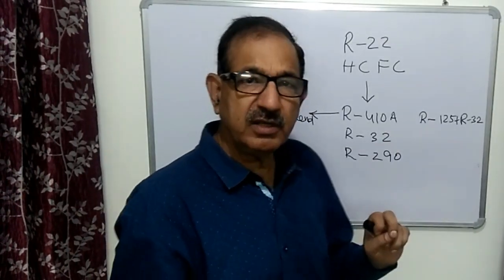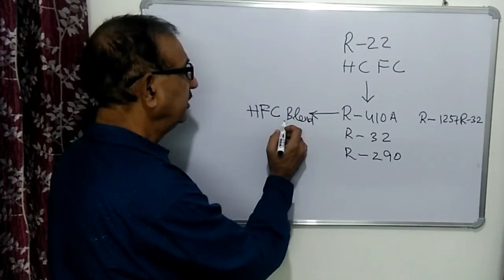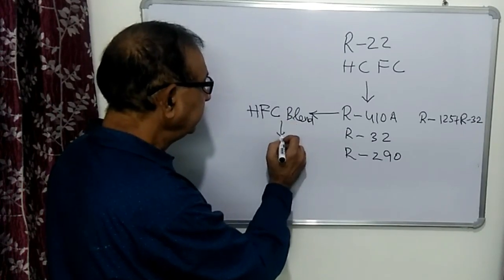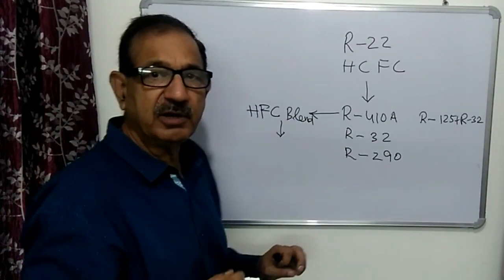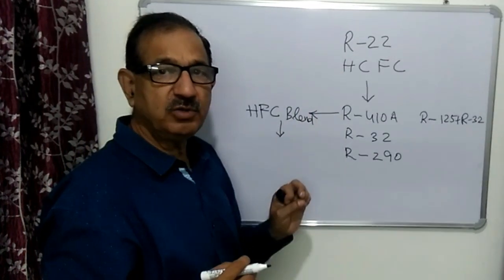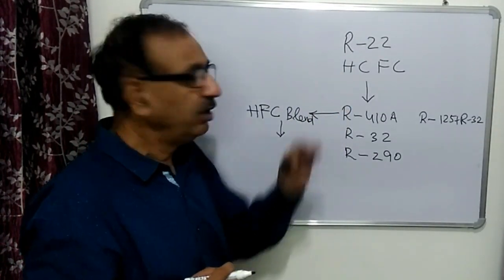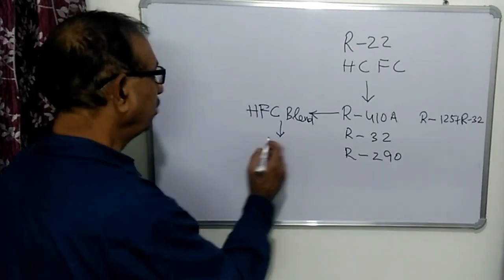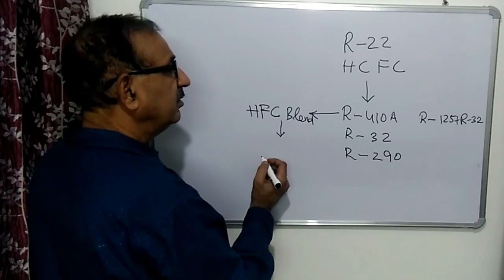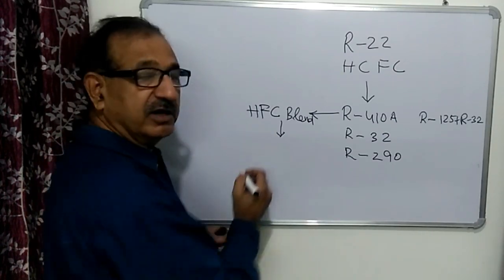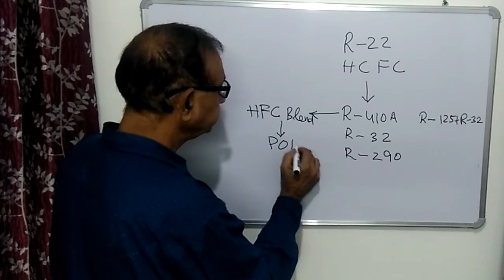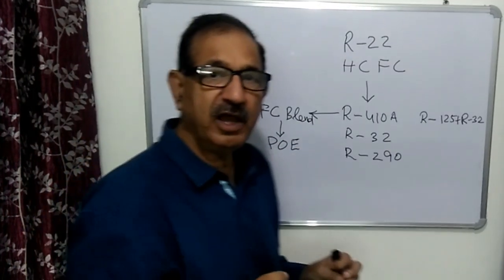R410A is a hydrofluorocarbon blend and it is not compatible with mineral oil, so we cannot replace R22 with R410A or R410A with R22 interchangeably. The oil used for this HFC refrigerant is POE oil, which is very hygroscopic.